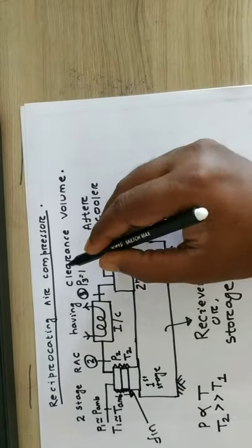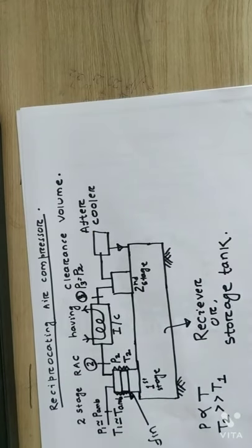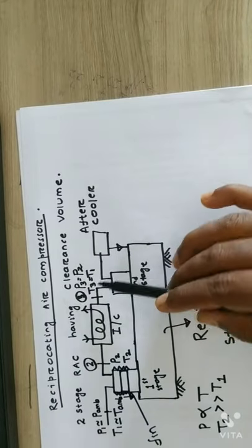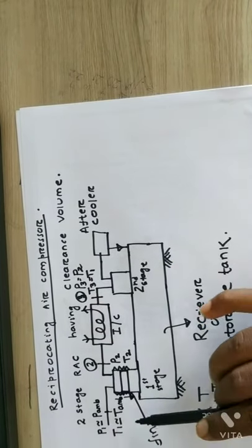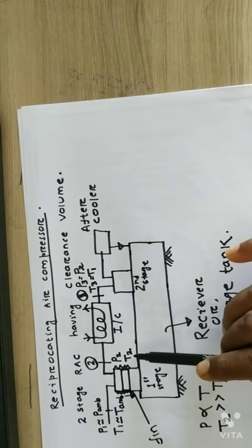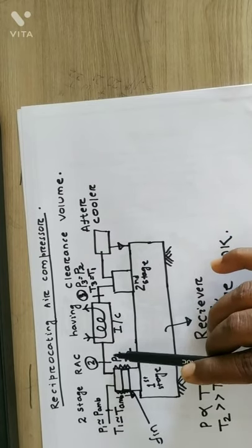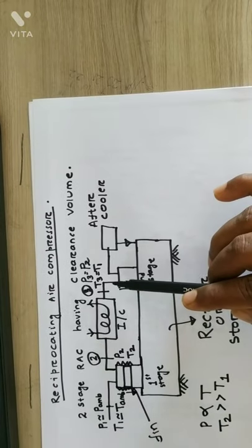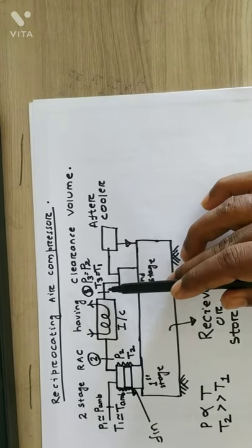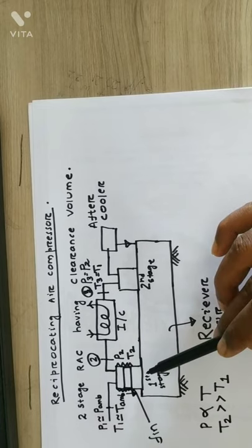At state point 3, the temperature T3 should be equal to T1, which is ambient temperature. The rise in temperature recorded by the first stage compressor at T2 is reduced by the intercooler — heat is released to the cooling water, and the compressed air temperature is reduced back to T1. This cooled compressed air is then fed into the second stage compressor.